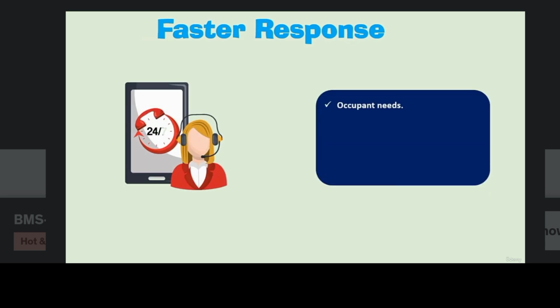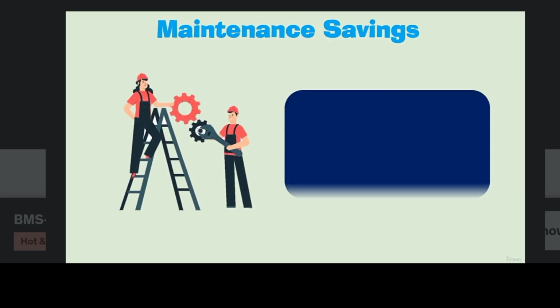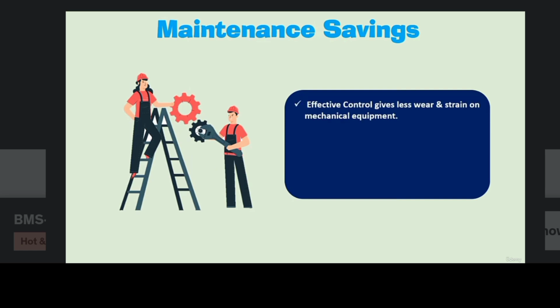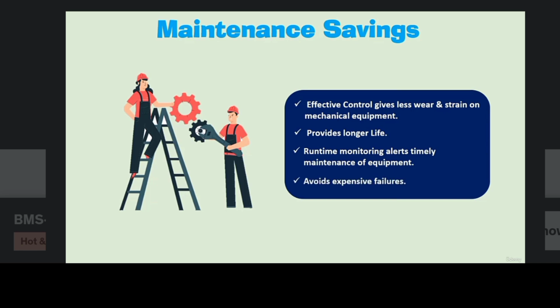Second benefit of BMS is a faster response to the occupant needs and user complaints, and also faster response to the trouble conditions. Third benefit is maintenance saving. As efficient control gives less wear and strain to the equipment, it also increases the life of the equipment. Runtime monitoring of the equipment also alerts timely maintenance, which avoids expensive failures.